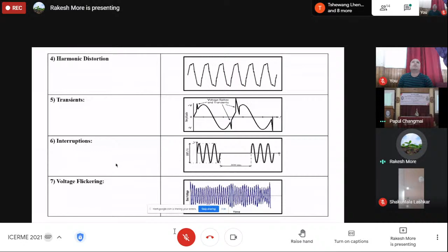Then the interruption, when a sudden load is switching off in the system. When a sudden or large load is switching off in the system, there is a reduction in the system voltage to 10% of the nominal RMS voltage level. This is known as the interruption. This interruption sometimes occurs for 60 seconds, or sometimes for more than 60 seconds. The causes behind the occurrence of interruption are faults on the transmission line, or the large inrush currents that flow in the transmission lines, which also cause the interruption.